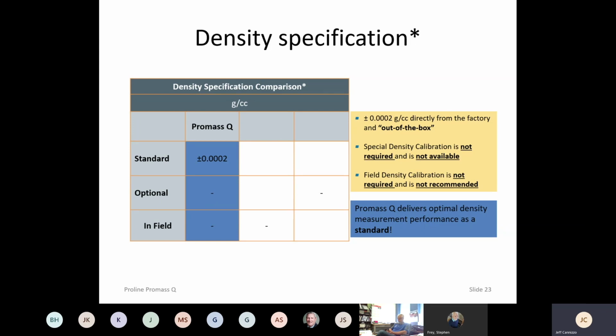But when we take it in the field, you're going to mount it right after a pump, right after a control valve. It's going to be vibrating. There's going to be lots of things going on that don't go on the test stand. So your accuracy of your instrumentation has to be able to absorb some of those field situations, and the actual accuracy that's delivered is not as good as the reference accuracy that you can achieve on the bench.